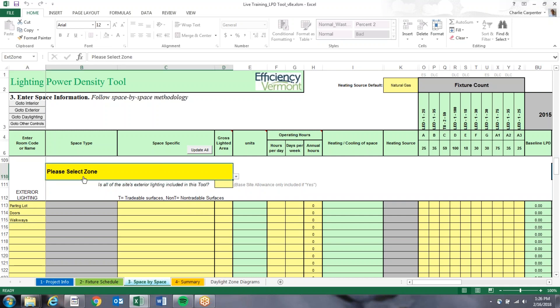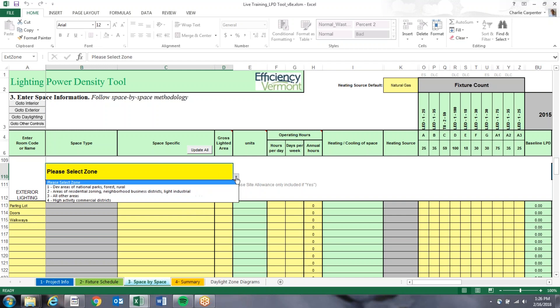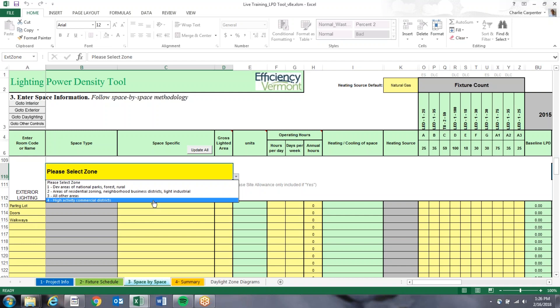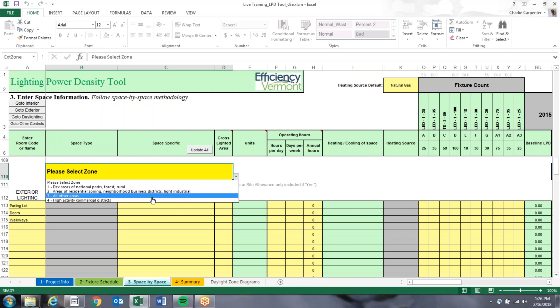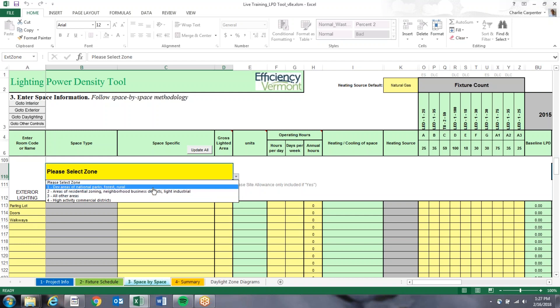Come to the big yellow tab and select the zone type. There are four zone types that determine how many watts are allocated per space type. Vermont has no zone fours — those are large metropolitan areas. Zone three includes Vermont's large downtowns like Burlington and Rutland. Zone two covers areas with a mix of residential and commercial, which represents most of the projects seen. Zone one covers rural areas and national parks, and some ski areas might fall there.